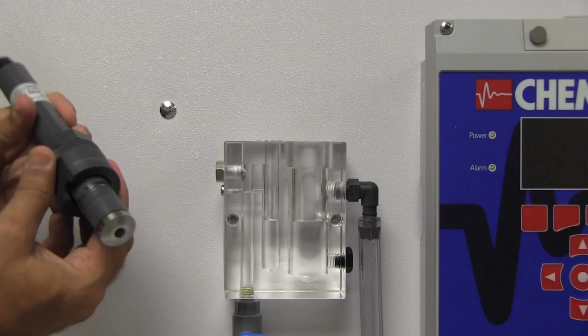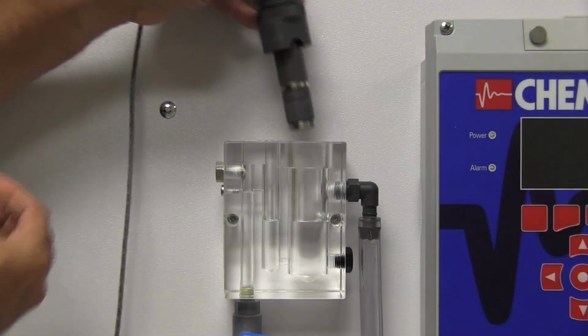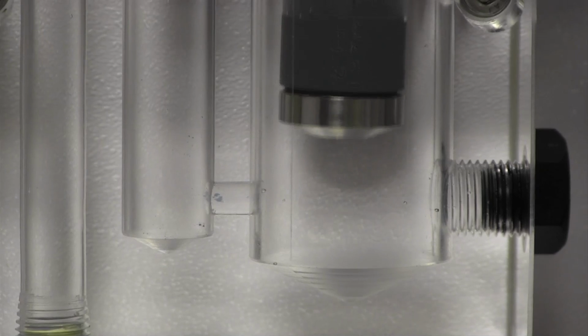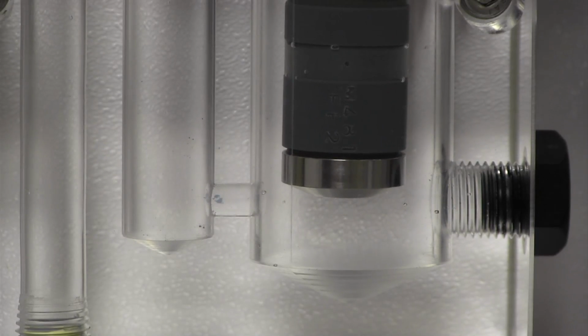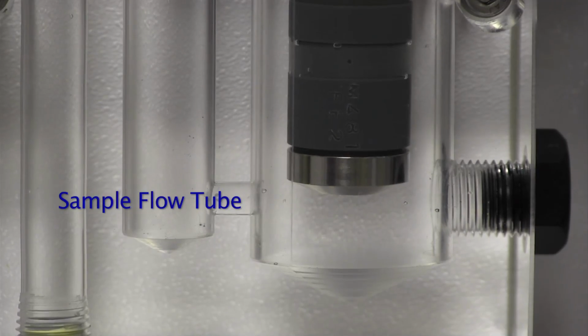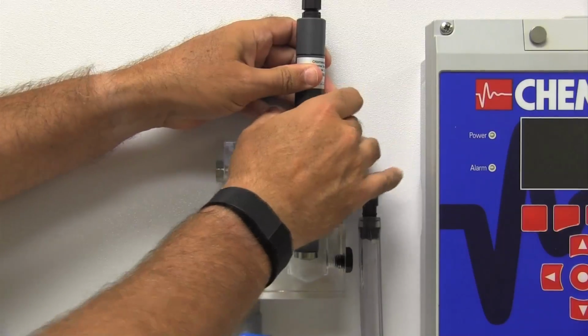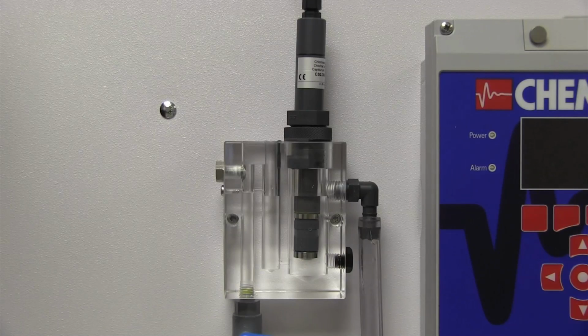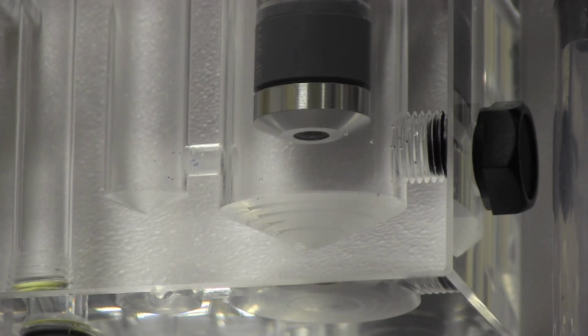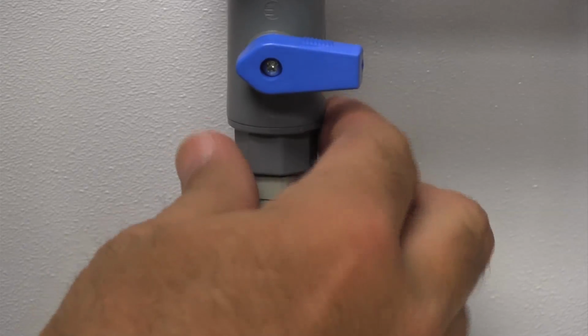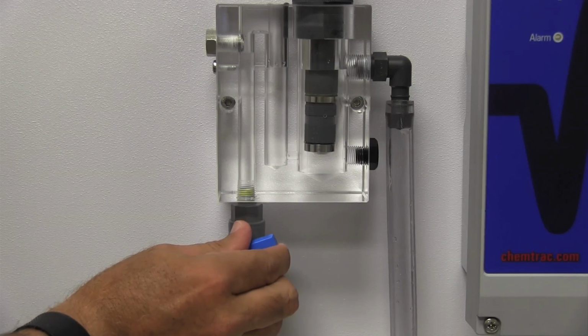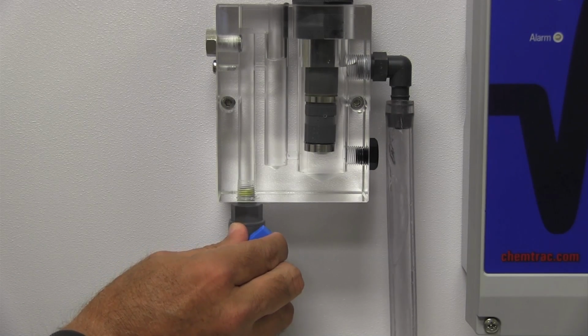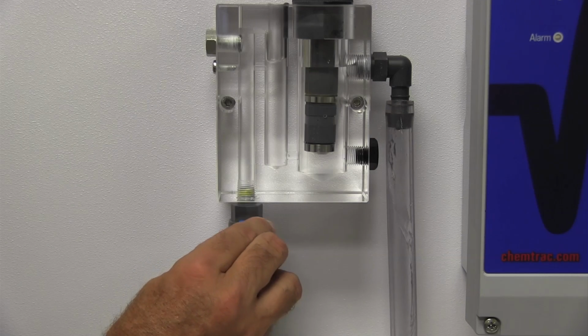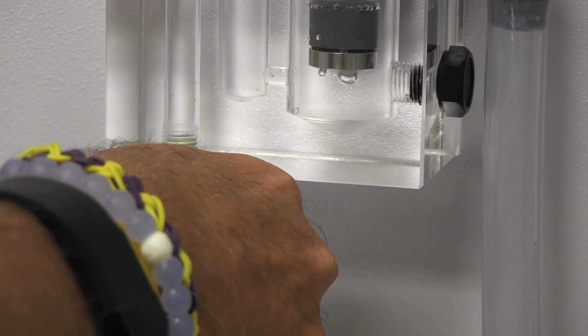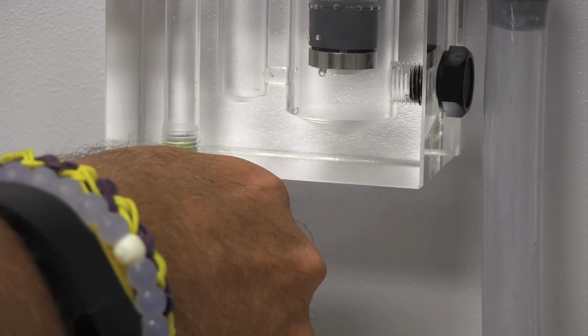When installing, slide the PVC fitting over the probe and then insert the probe into the flow cell. Adjust the PVC fitting so that the probe tip is positioned just above the horizontal sample flow tube near the bottom of the chamber. Water exiting this tube needs to pass across the tip of the probe to prevent bubbles from forming on the membrane, which could subsequently impact the accuracy of the chlorine reading. Connect the sample tubing to the inlet fitting on the flow cell and start the flow of water. The recommended minimum flow rate is 500 milliliters per minute, but higher flow rates of 700 to 900 milliliters per minute may be needed to keep the membrane free of bubbles.